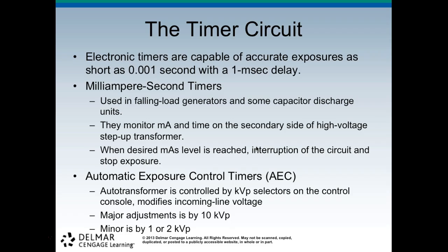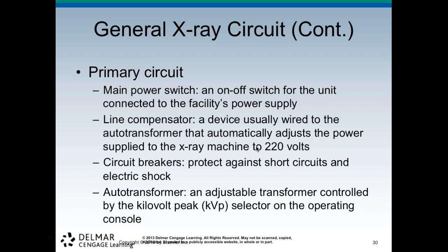There is an autotransformer, controlled by kVp selectors on the control console. It modifies the incoming line voltage. There are major adjustments, where you can jump 10 kVp at a time, and minor adjustments, from 1 to 2 kVp at a time.